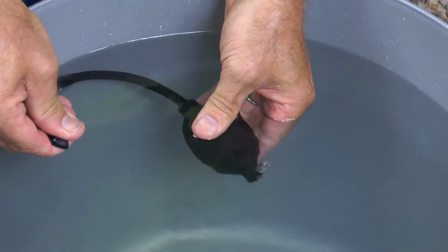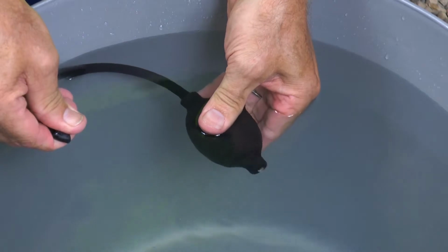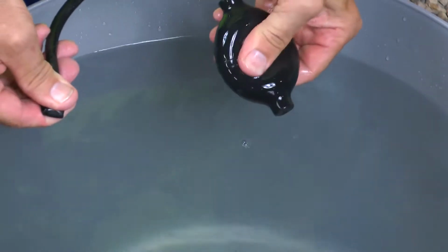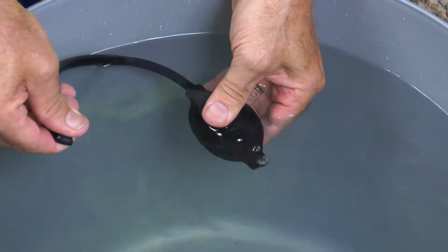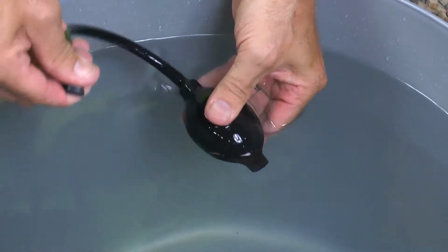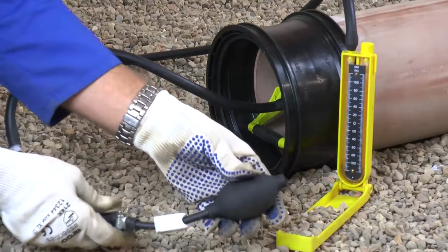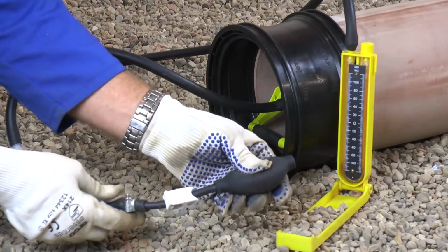The pressure pump can also be a cause of air leakage. Pinch one end of the pump tubing and pressurize. Check for air coming out of the pump. And check that any valve or clip is in place, closed and is working correctly.